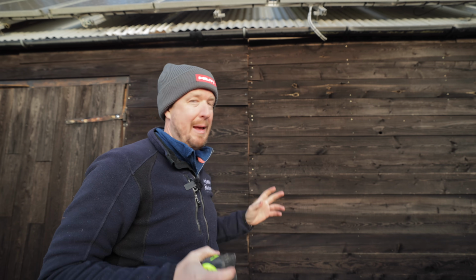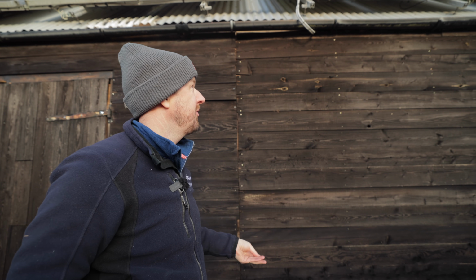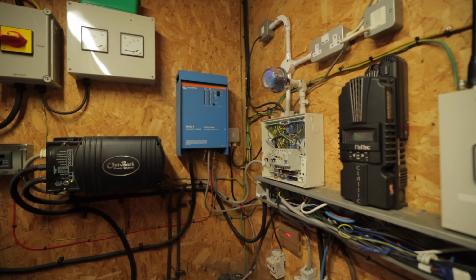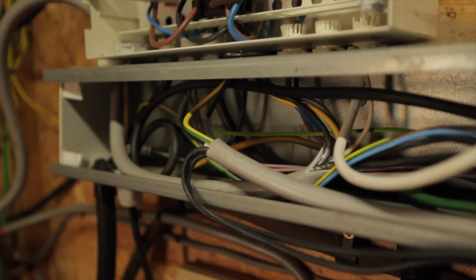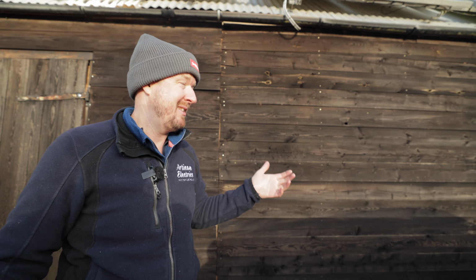If we wanted to install an MCS certified approved install here, which we don't actually have to because it's off-grid, you can kind of do what you want, but that's the danger. It's so dangerous when people think, oh, I'm off-grid, so all the rules don't apply. It doesn't matter whether you're off-grid or on-grid, if you're generating electricity, it needs to be safe. Unfortunately, so many people, when they go off-grid, think they can throw the rule book out completely and install a system that's not even safe, definitely not neat, and it's debatable whether it even works as intended.